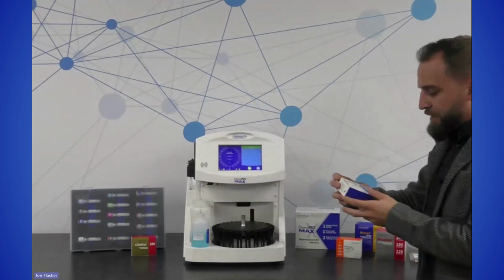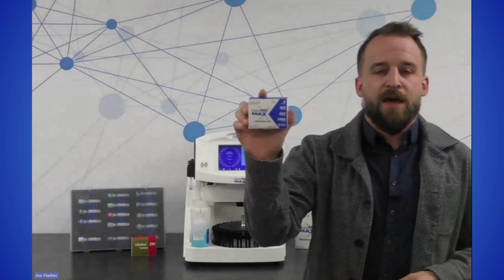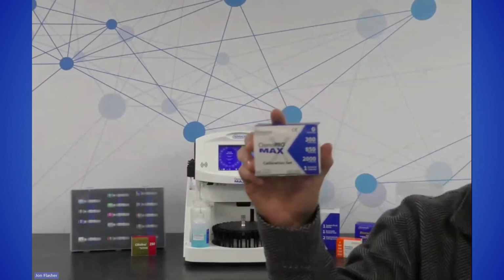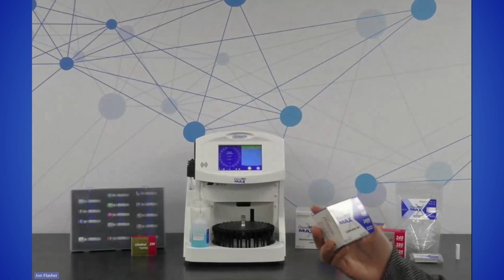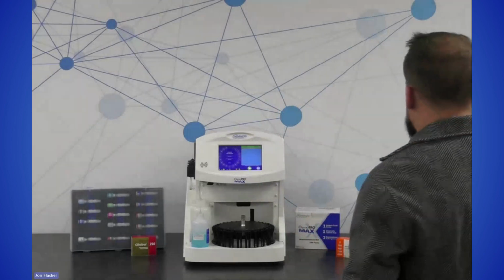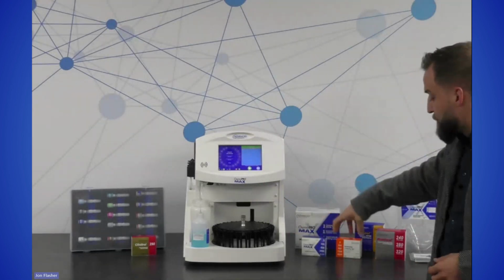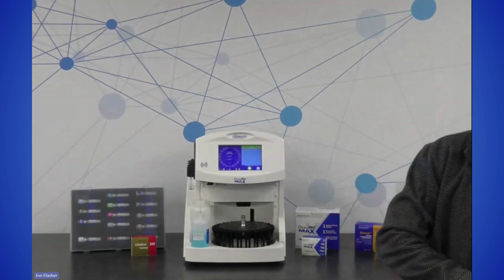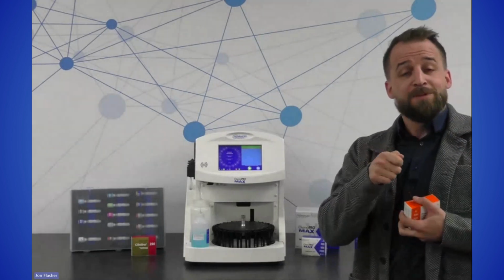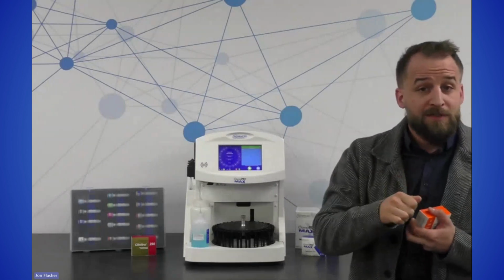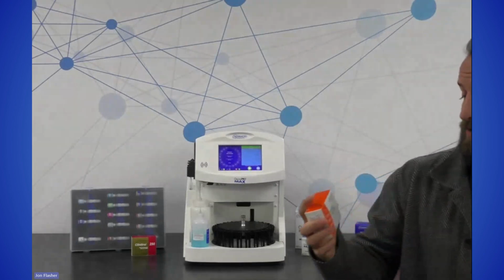What else you're going to get is this OsmoPRO MAX calibration set. This calibration set comes with 4 levels: 0, 300 milliosmol, 850 milliosmol, and 2000 milliosmol standards, as well as an ampule opener. So when you're cracking open those glass ampules, if you're familiar with those, you can safely do that without worrying about any cuts or any risk there.